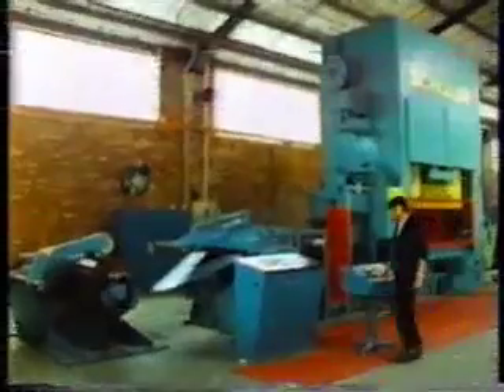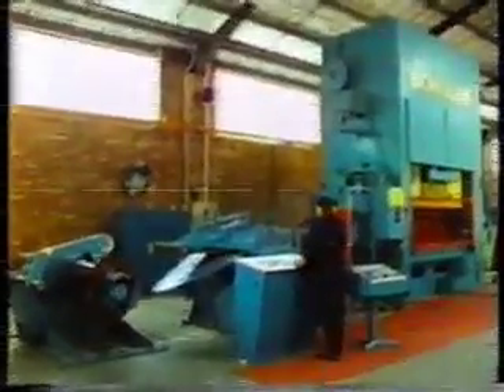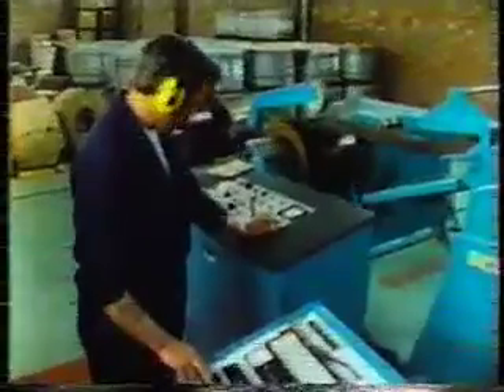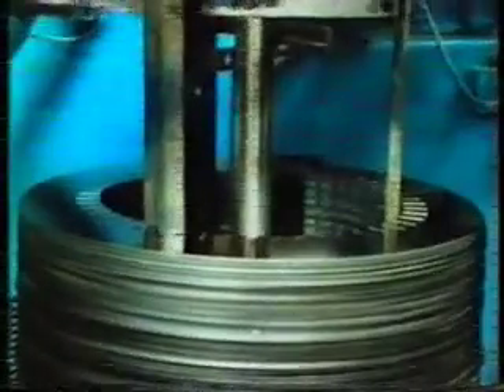At the heart of every alternator are the laminations. They carry the windings on both the rotor and the stator. This is where the manufacturing process begins. The laminations are made from thin insulated steel of a very high grade. They're mass-produced on an automatic blanking press. Then on to the notching press, where the characteristic alternator slots are punched in, leaving the separate inner rotor and outer stator laminations.